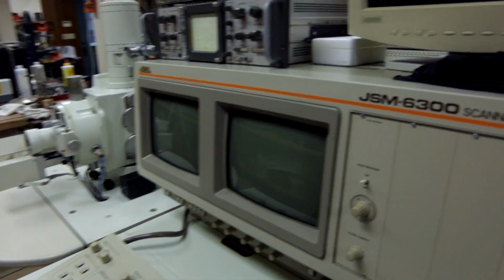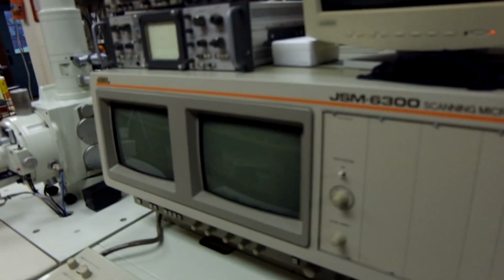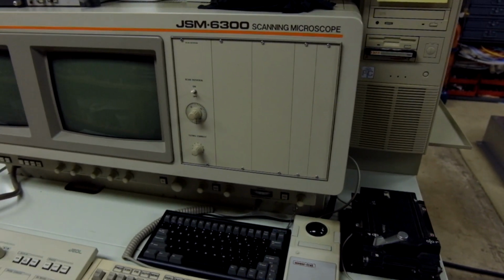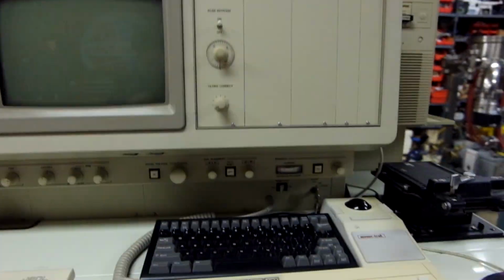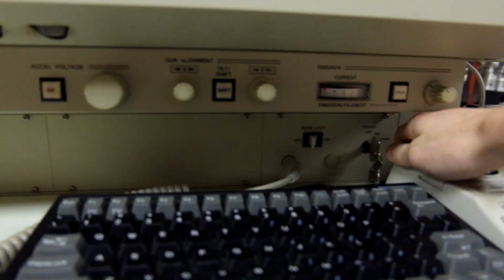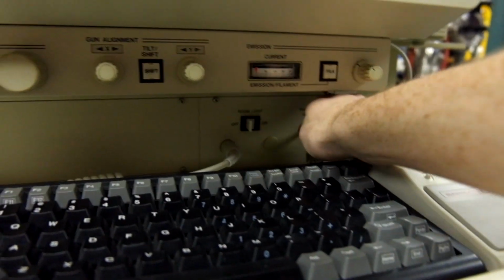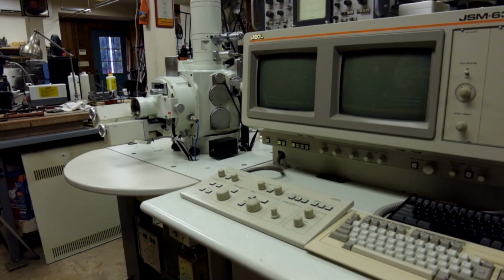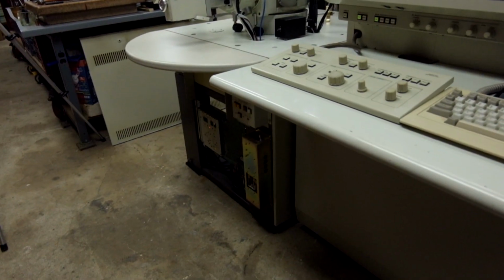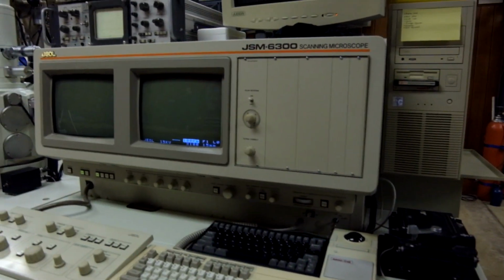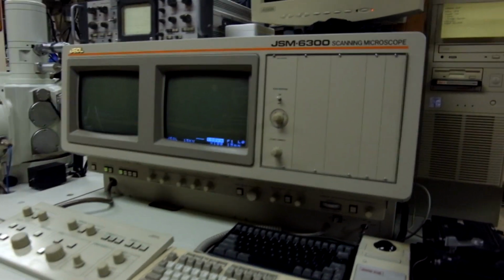So now that we have the power on, the water chiller, and the nitrogen on, we can go ahead and turn the actual microscope on. Down here there's a little key switch, just like starting a car. You put it on the on setting and then flip it to start. And the CRTs are slowly going to come on. You heard the rotary pump just come on, and some lights are turning on down there on the vacuum control panel. So things are happening. The first digital CRT is coming on.